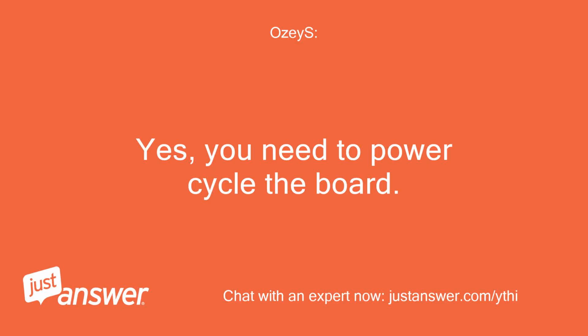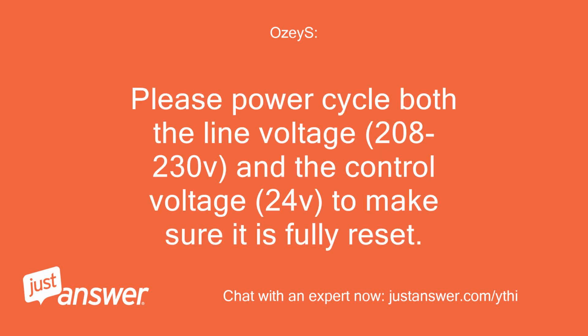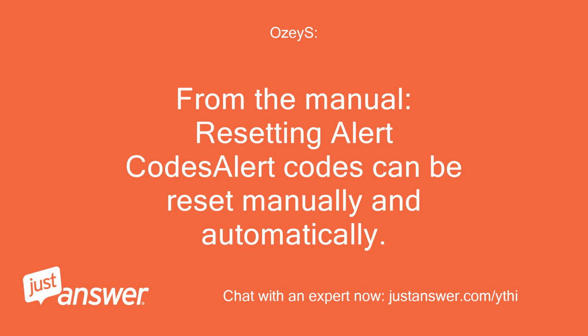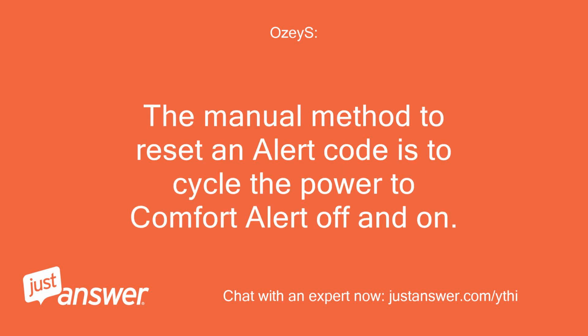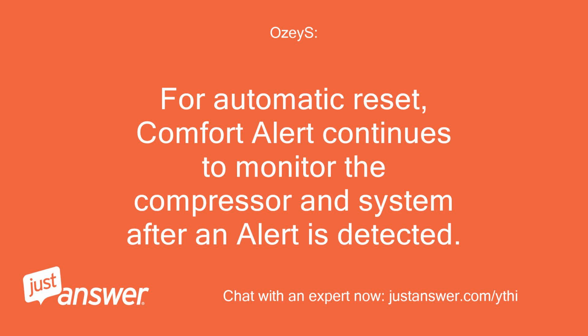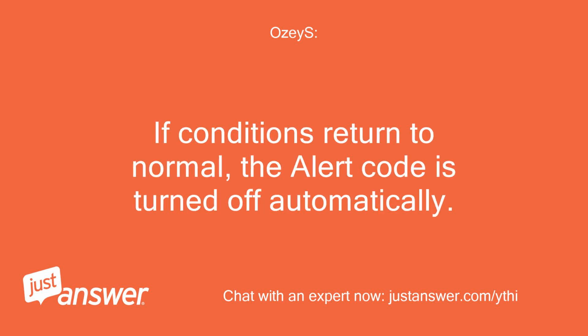Yes, you need to power cycle the board. Please power cycle both the line voltage, 208/230V, and the control voltage, 24V, to make sure it is fully reset. From the manual, alert codes can be reset manually and automatically. The manual method to reset an alert code is to cycle the power to Comfort Alert off and on. For automatic reset, Comfort Alert continues to monitor the compressor and system after an alert is detected. If conditions return to normal, the alert code is turned off automatically.